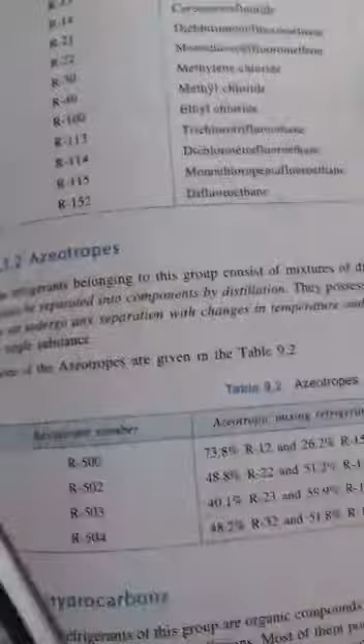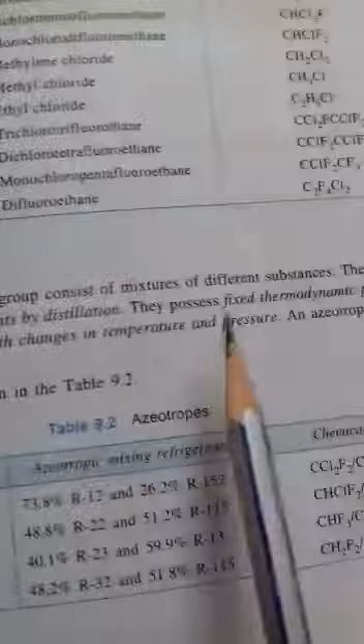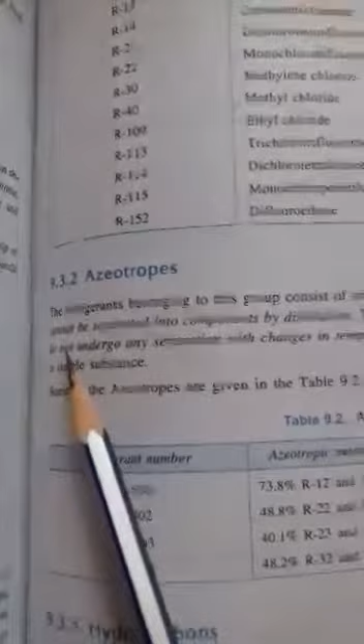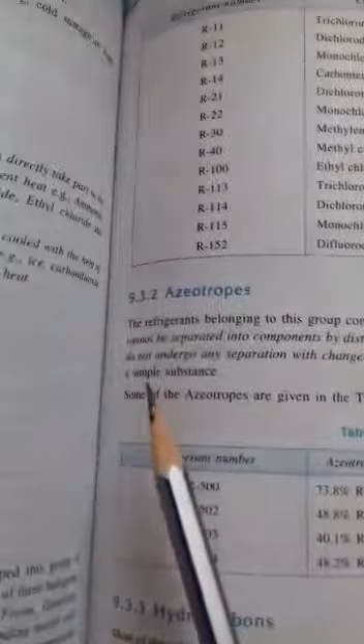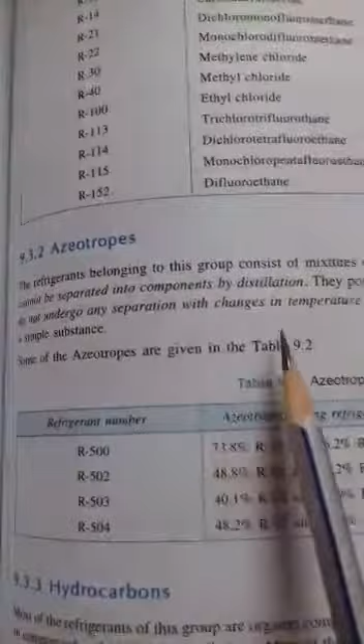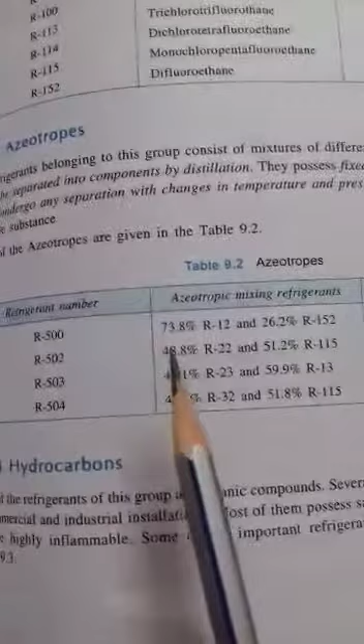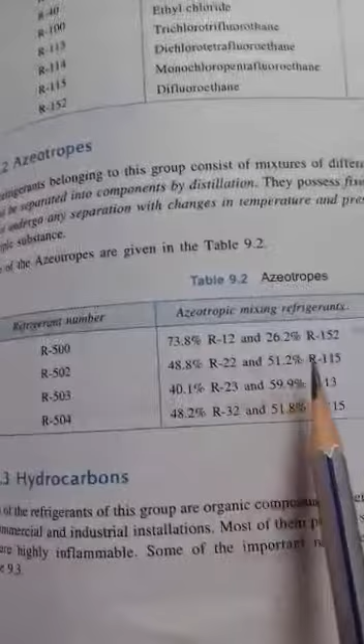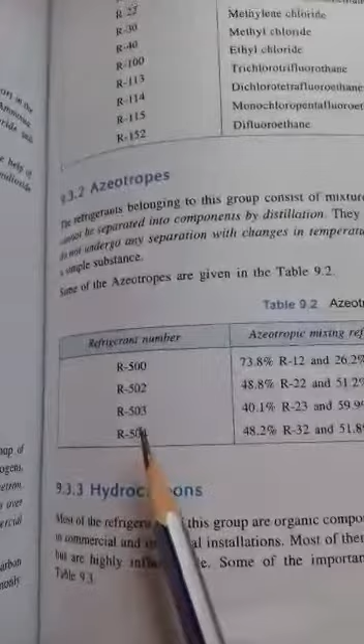Then come azeotropes. The refrigerants belonging to this group consist of mixtures of refrigerants which cannot be separated into components by distillation. They possess fixed thermodynamic properties and do not undergo any separation with changes in temperature and pressure. An azeotrope behaves like a simple substance. Some of the azeotropes are given in the table: R500, that is 73.8% R12 and 26.2% R152. Then R502, 48.8% R22 and 51.2% R115. Then R503, 40.1% R23 and 59.9% R13. R504, 48.2% R32 and 51.8% R115. These are the azeotropic mixtures.